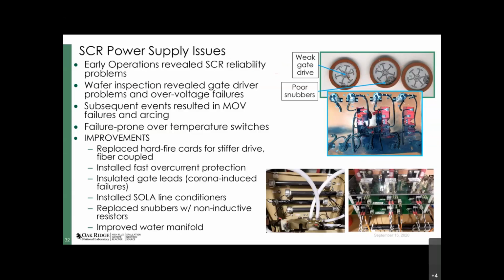Indeed, after we identified this, we ran it for a little while longer, and lo and behold, we opened up one of the snubbers and it looked like this in the blue box. Basically the MOVs had gotten so hot because the snubber was not doing its job. This is basically an RC snubber, and the MOVs were taking the majority of the snubber duty, and they weren't designed to do that. So they got so hot the MOV billet actually melted through the case, and eventually it flashed over and tripped.